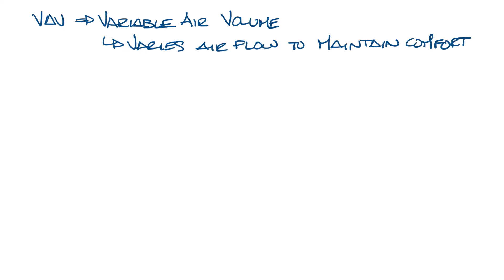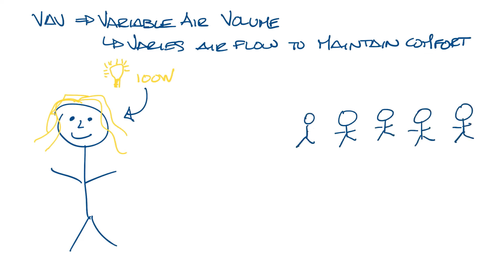When the room is empty, there's no load in the space, so it doesn't take much air volume to maintain the comfortable temperature. But when the conference room fills up, it requires more airflow. People are approximately the equivalent of a 100 watt light bulb. So when you put 10 people in the conference room, you have a thousand watts more heat in the room and you need more air to maintain a comfortable temperature in the space.